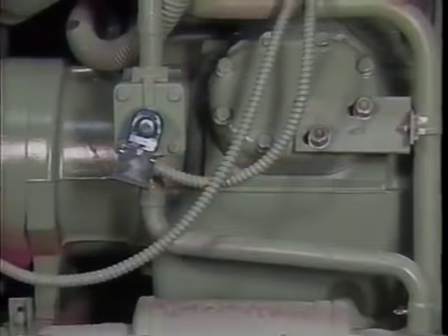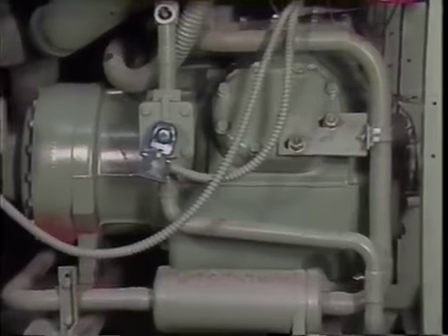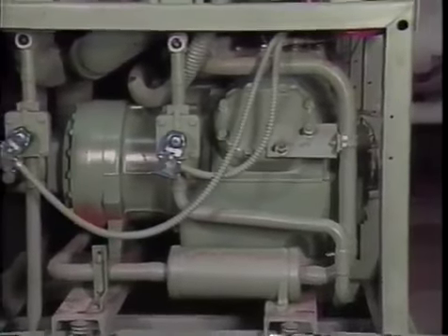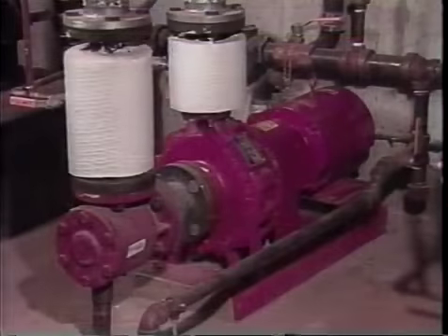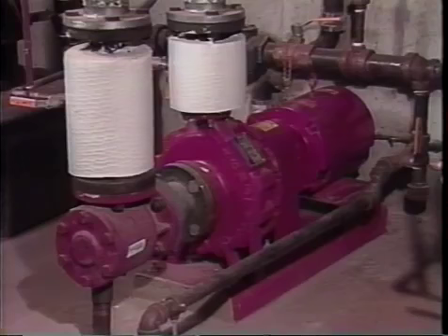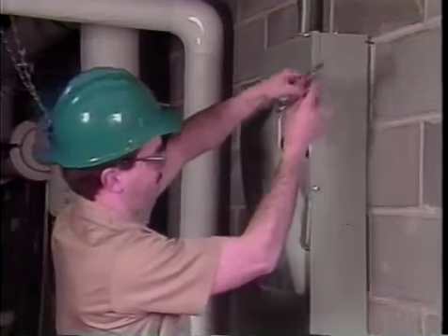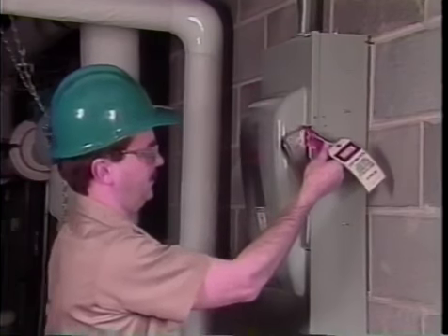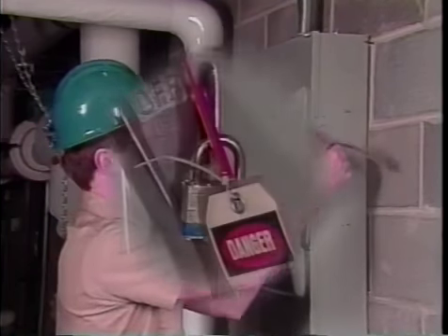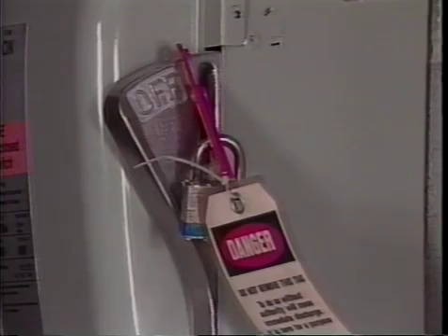Remember, safety is the most important part of your job. Working on air conditioning, refrigeration, or heating systems means working on components that are pressurized, rotating, and either thermally or electrically hot. So be careful. Before performing mechanical service, shut off all the power. Open, lock, and tag all disconnects. Use extreme caution when troubleshooting electrically live components.